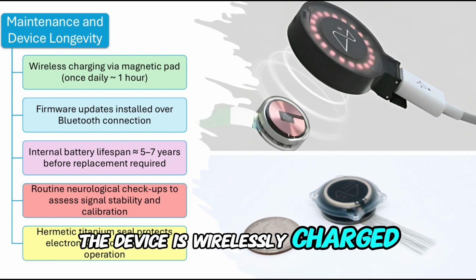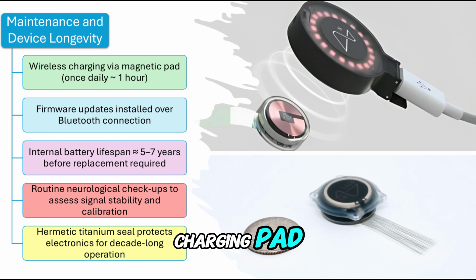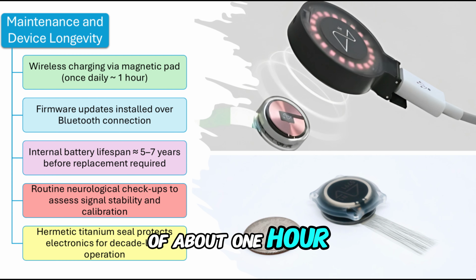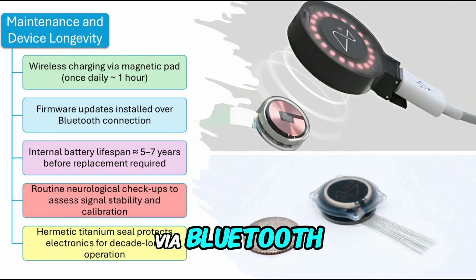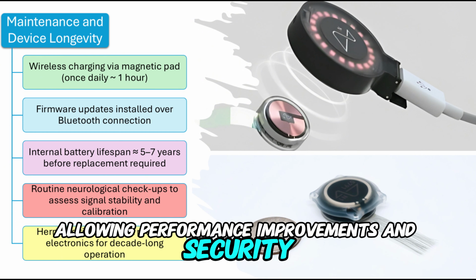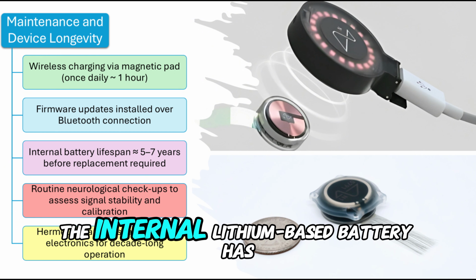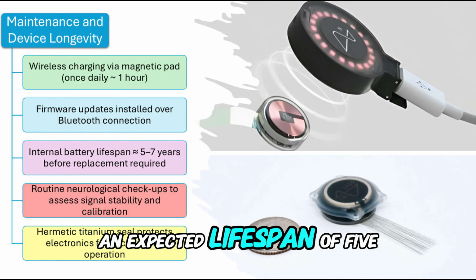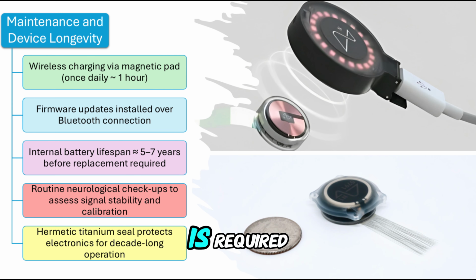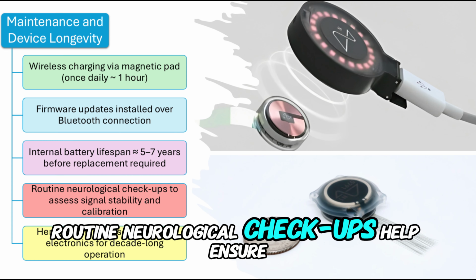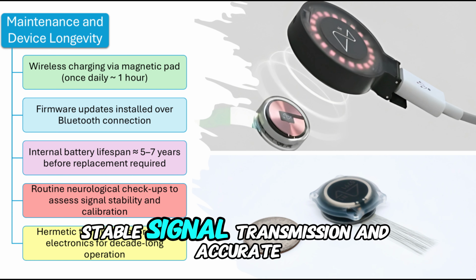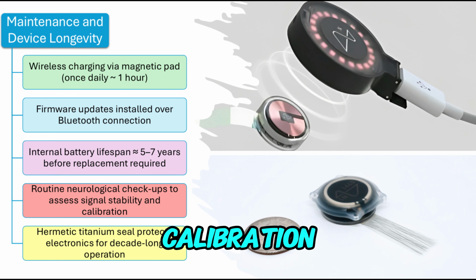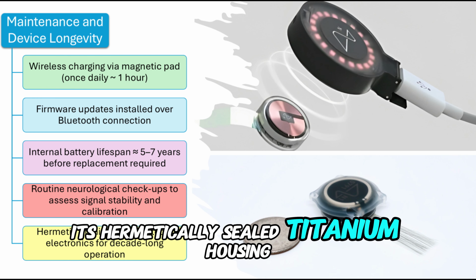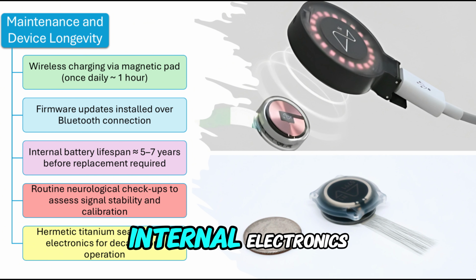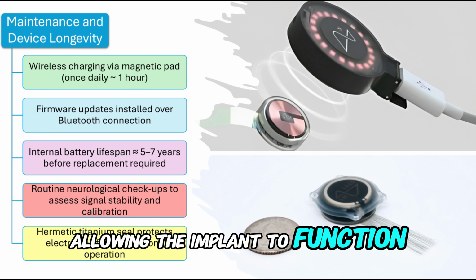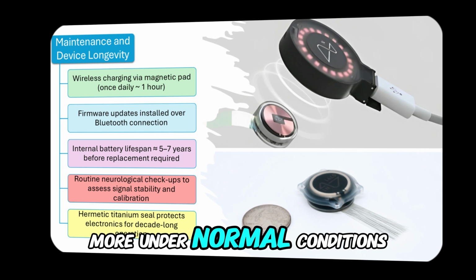The Neuralink N1 implant is designed for long-term, low-maintenance operation. The device is wirelessly charged each day using a magnetic charging pad with a typical charge time of about 1 hour. Firmware updates are installed remotely via Bluetooth, allowing performance improvements and security updates without surgery. The internal lithium-based battery has an expected lifespan of 5 to 7 years before replacement is required. Routine neurological checkups help ensure the device maintains stable signal transmission and accurate calibration. Its hermetically sealed titanium housing provides durable protection for the internal electronics, allowing the implant to function reliably for a decade or more under normal conditions.